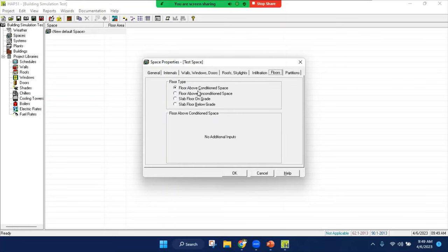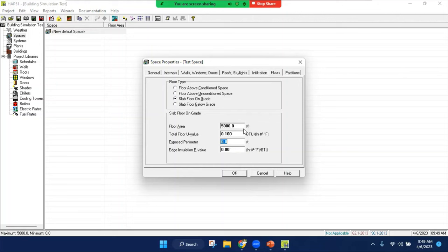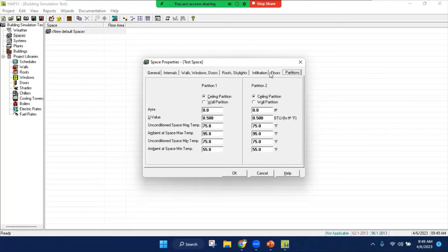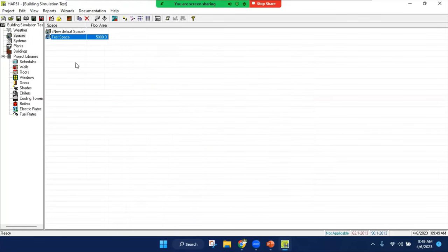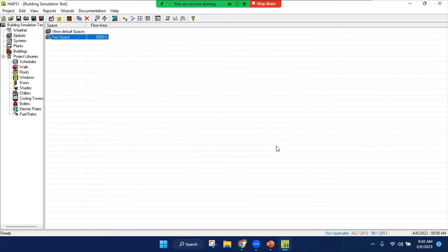Let's go to the floors. I'm going to pick slab on grade. I have total area, U-value for exposed perimeter. Let's put the perimeter of the building, which is 300 feet, because I have 100 on one side, 50 on the other side, so 150 multiply by 2 to make it complete 300. Is it insulated? Let's call it no. I'm going to skip partitions for this example, but you can add partitions with certain area. Make sure your file is saved. At this point we are done with the spaces.